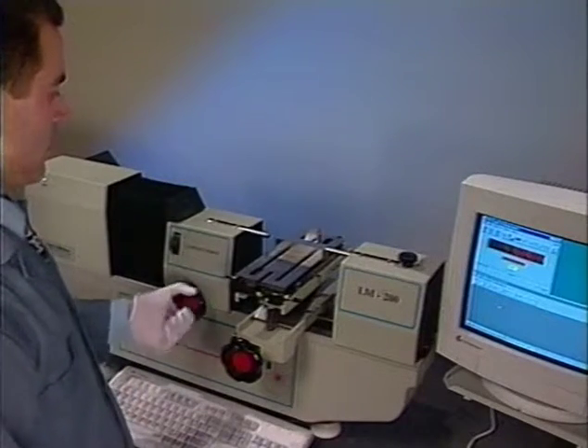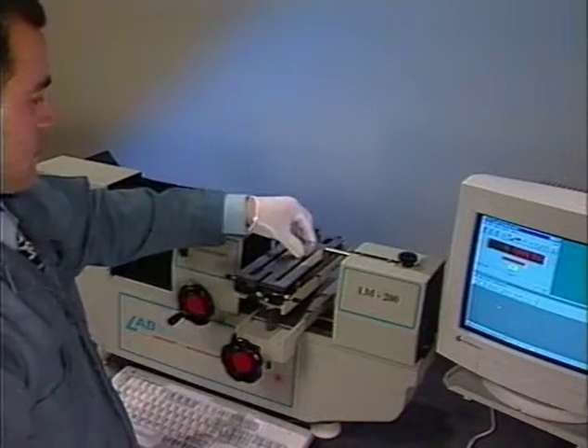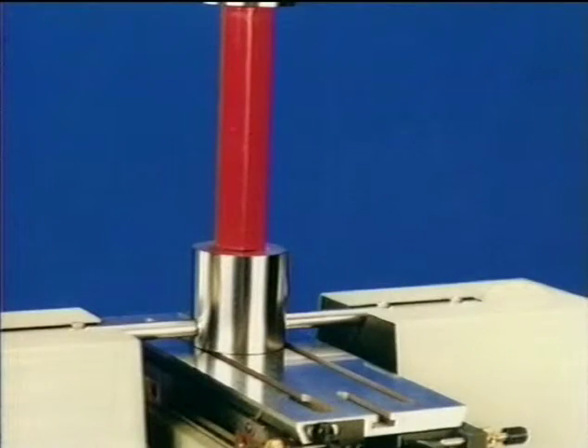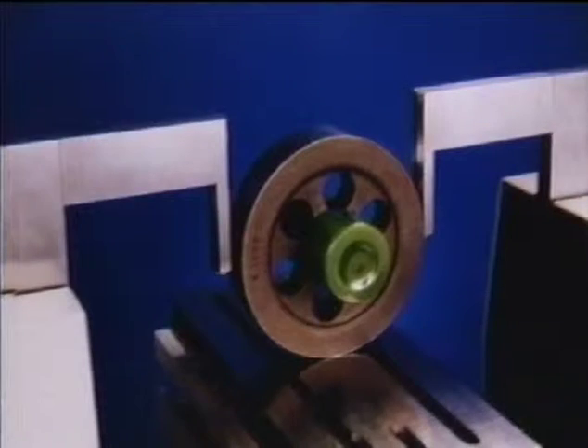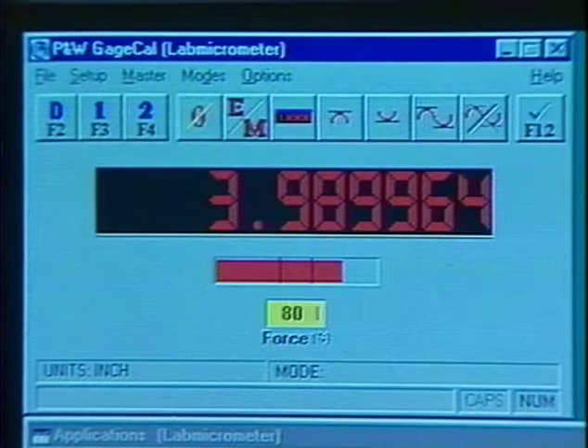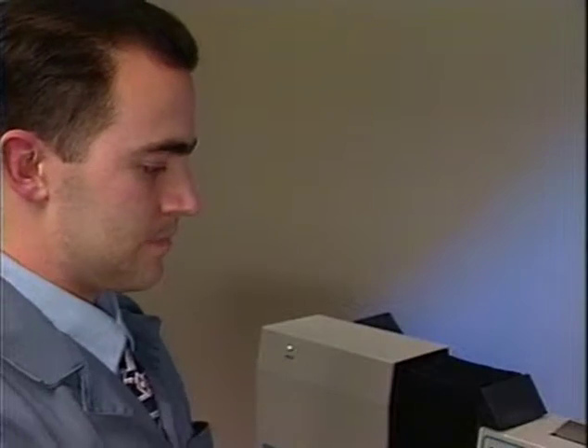Using different size gauge blocks allows the user to vary the size of the range to meet specific needs. Now that the system is calibrated, any external dimension specimen that falls within the calibrated range can be placed between the anvils. Once the headstock is advanced far enough to generate a go from the on-screen measurement indicator, the absolute measurement traceable to NIST is displayed. It's that simple.